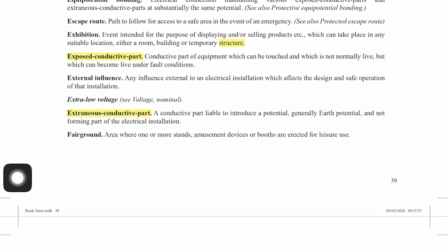Extraneous conductive parts is a conductive part liable to introduce potential, generally earth potential, and not forming part of the electrical installation. So this is a metallic part that comes generally out of the ground. It could be a cast iron soil pipe, a gas pipe, a water pipe, like a lead pipe or something like that.